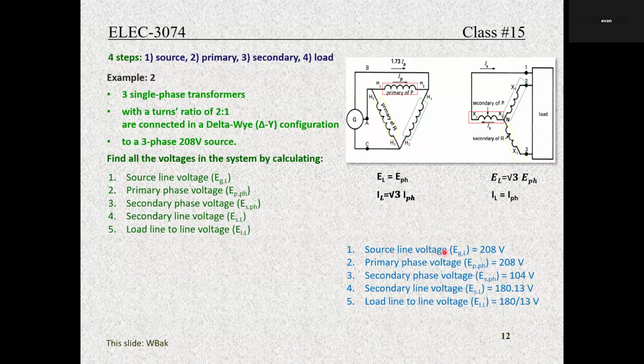Source voltage, line - well, we're told that it's a 208 source, which means it's the line voltage, 208. So between those two lines we have 208, between those two lines we have 208, and between these two lines we have 208. So 208, 208, 208, because phase voltage is equal to line voltage in delta configuration. Different case in the Y, but we're not looking at the Y yet - we're looking at this side first, because they're asking for source line voltage and primary phase voltage. Primary phase voltage equals the line voltage, so it's also 208. We don't even need a calculator for that one.